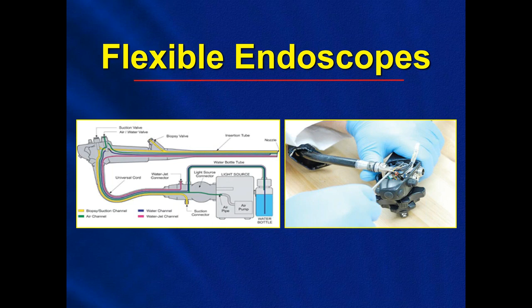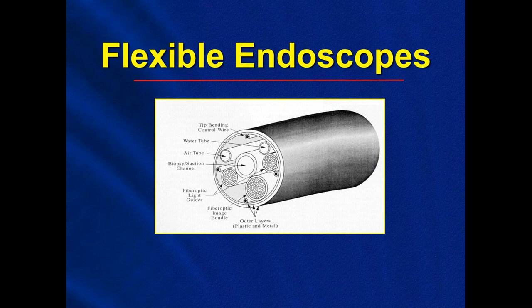Now take a look at this photo that shows a cutaway section of the tip of a scope, which displays some of the things that may be inside a flexible scope, depending, again, on the type of scope that you're using. Things such as light bundles that will carry the light to the tip, image bundles, or maybe even tiny digital cameras in the tip of the scope for optics, air, water, biopsy channels, suction channels, all surrounded by the bending wires and the outer sheath of the scope. So very intricate, very delicate inner workings wrapped inside that nice, neat package of the outer sheath, which makes the scope look pretty, but a lot going on inside the scope.